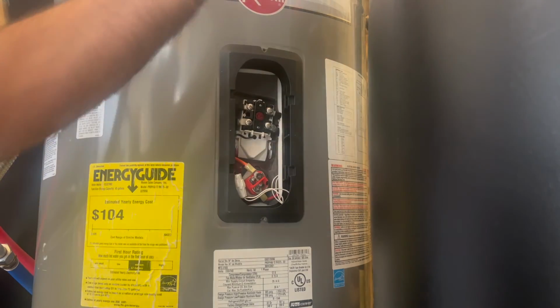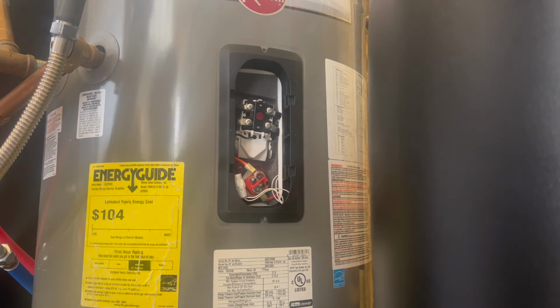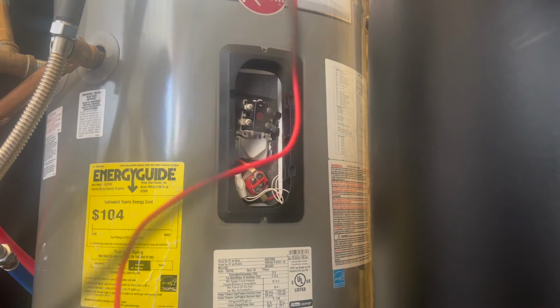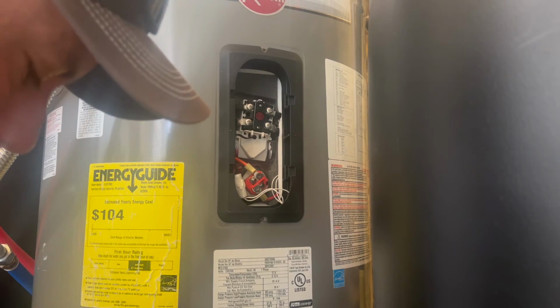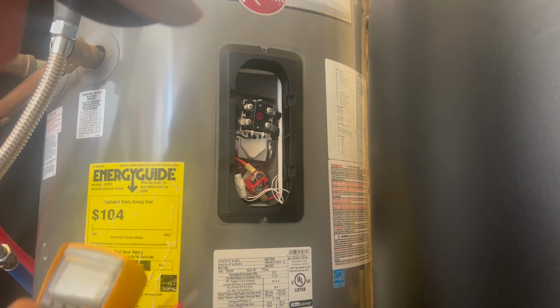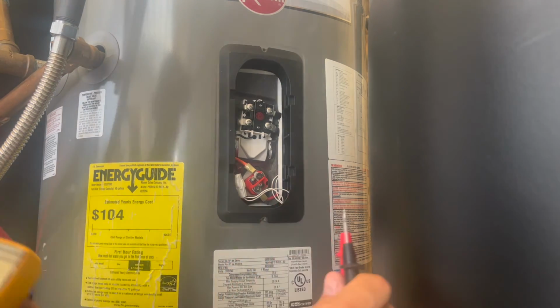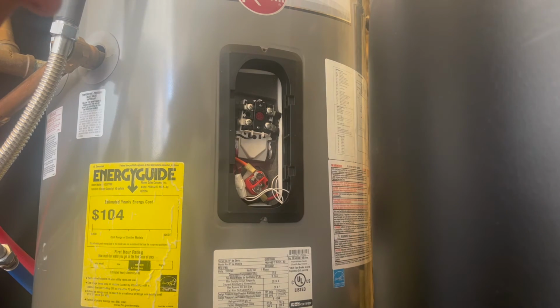And let's see here. I want to show you something on this. We may go back into test mode because I forgot to mention one thing, and that is you can check the upper and lower temperatures on these thermistors. It'll tell you if you've got a problem as well. If your water's coming out hot, but the thermistor says it's not hot inside the tank, you likely have a sensor problem or a wiring problem.